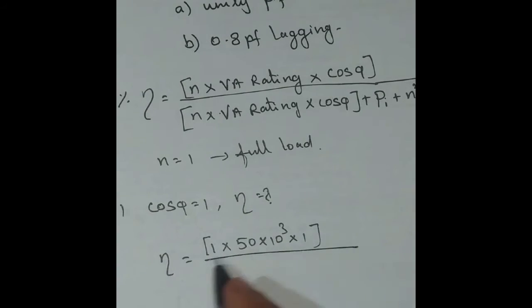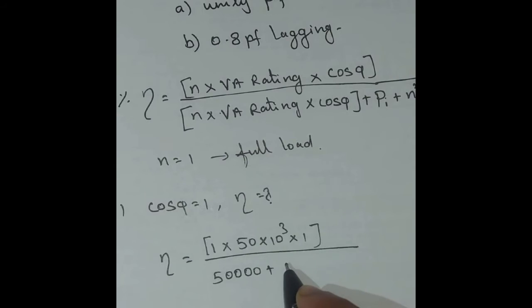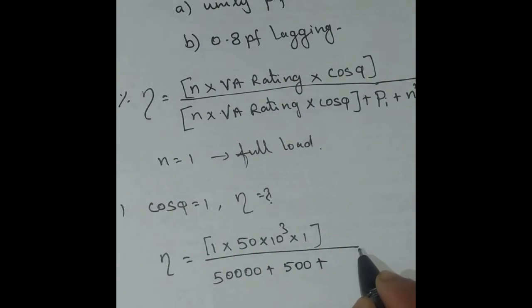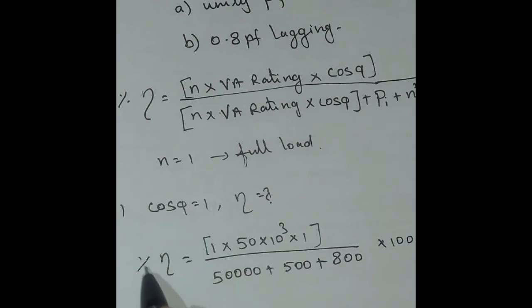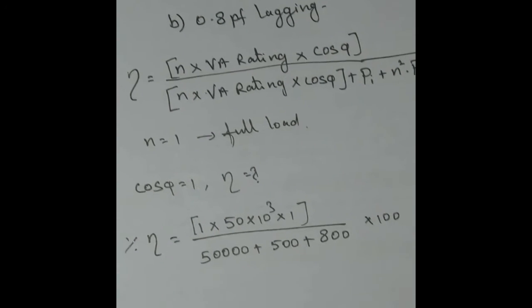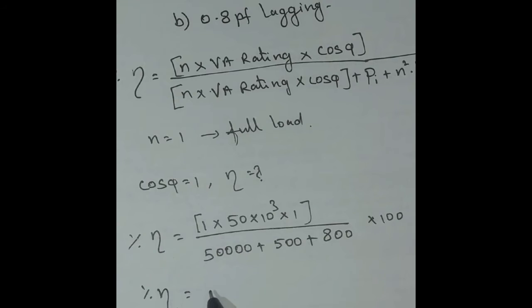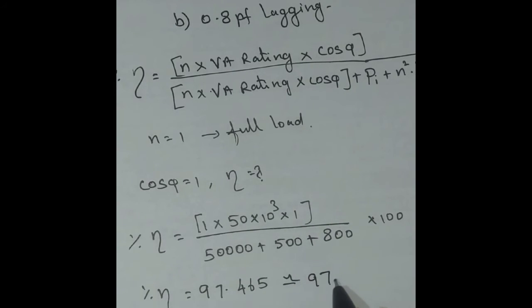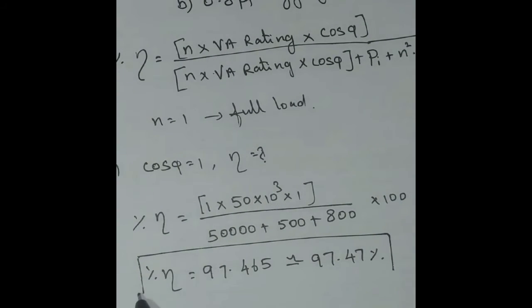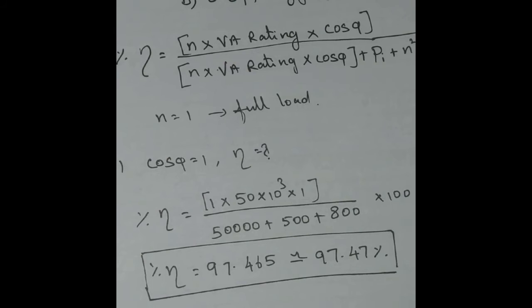The numerator is 50,000. The iron loss is 500 watt and full load copper loss is 800 watt. Multiplying by 100 for percentage, solving gives efficiency of 97.465%, or approximately 97.47%. This is the efficiency at unity power factor.